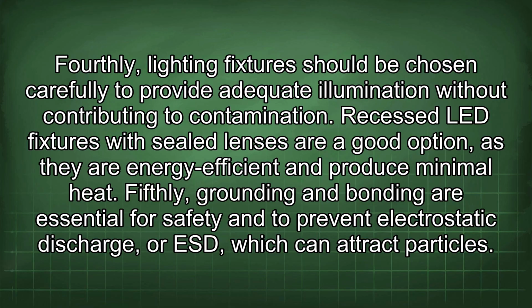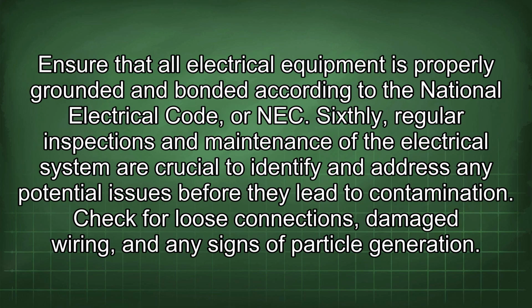Fifthly, grounding and bonding are essential for safety and to prevent electrostatic discharge, or ESD, which can attract particles. Ensure that all electrical equipment is properly grounded and bonded according to the National Electrical Code, or NEC. Sixthly, regular inspections and maintenance of the electrical system are crucial to identify and address any potential issues before they lead to contamination. Check for loose connections, damaged wiring, and any signs of particle generation.